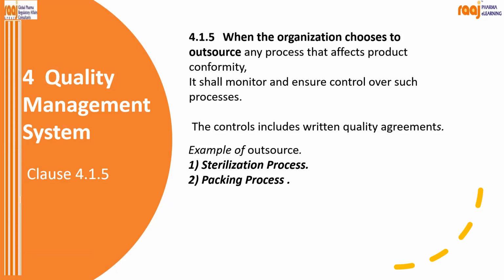So whatever studies or activities are outsourced, you have to define that process. You have to write the SOP and make the quality agreement with those outsourced parties, and define how you monitor the control. It shall monitor and ensure control over such processes, and these controls include written quality agreements. So whenever you outsource the sterilization process, packing process, stability studies or any testing, you have to establish a quality agreement with the third party, the outsourced party.